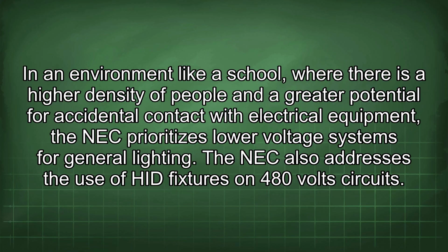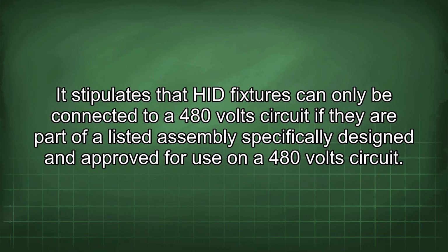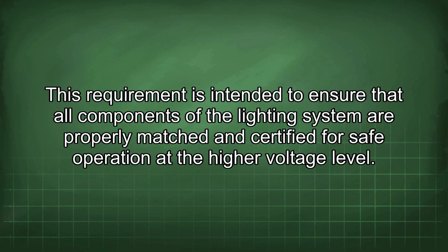The NEC also addresses the use of HID fixtures on 480-volt circuits. It stipulates that HID fixtures can only be connected to a 480-volt circuit if they are part of a listed assembly specifically designed and approved for use on a 480-volt circuit. This requirement is intended to ensure that all components of the lighting system are properly matched and certified for safe operation at the higher voltage level.